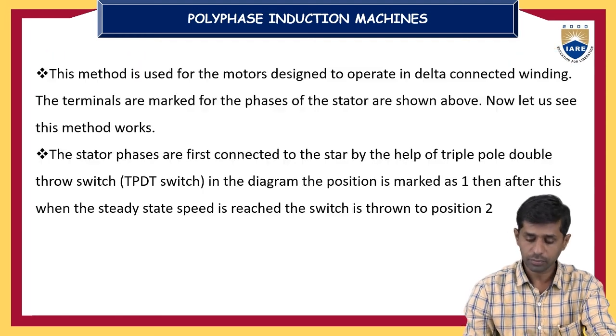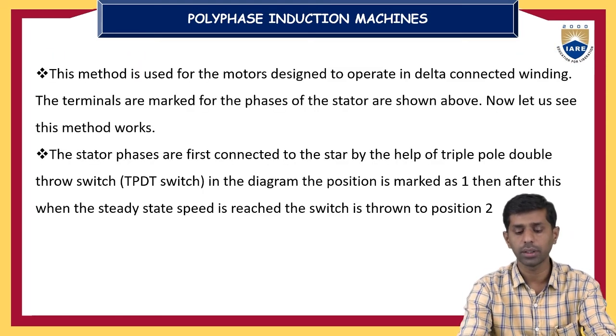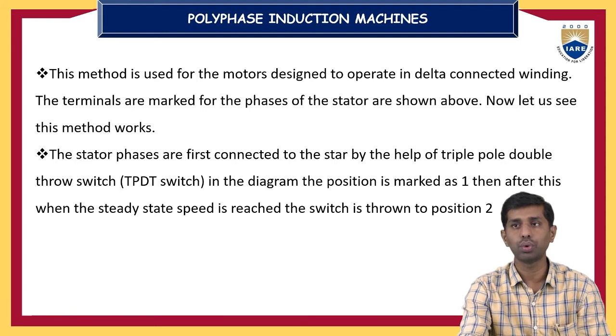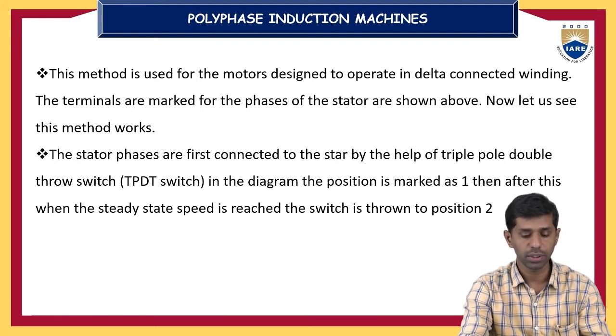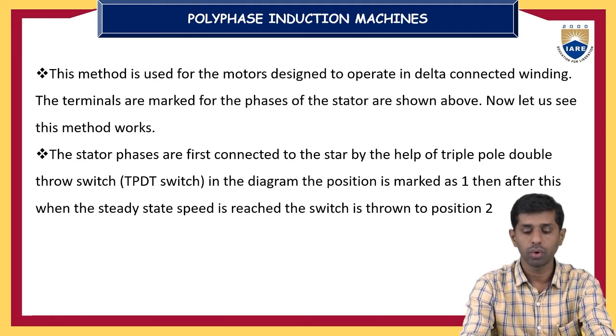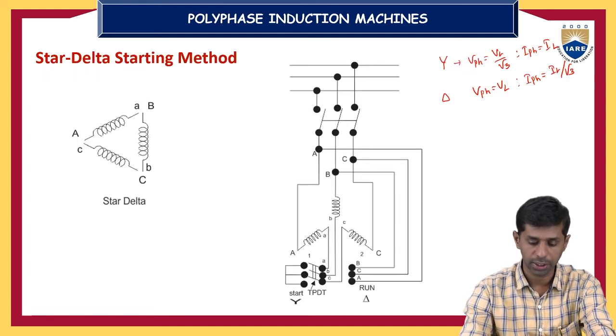So at the time of starting in this method, our intention is to limit the starting current. This method is designed to operate with a delta connected winding. The terminals are marked for the phases of the stator as shown above. Now let us see how the network will operate.